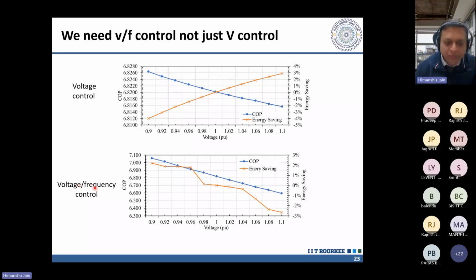But if you change voltage and frequency in the same ratio, say 10% change in both, which is what most inverter air conditioners are capable of doing today, you see the behavior changes. Now, as I reduce my voltage, I do see a few percentage savings in terms of energy.